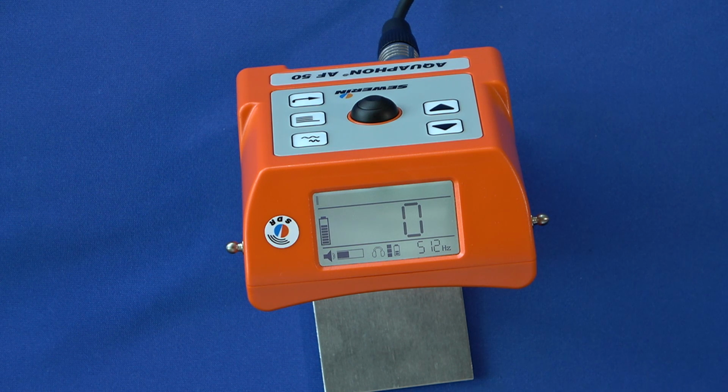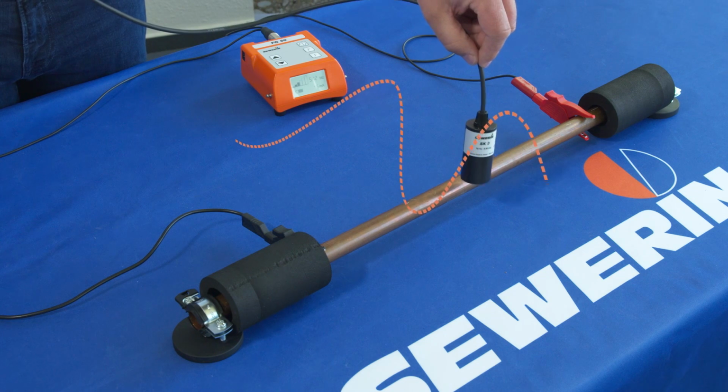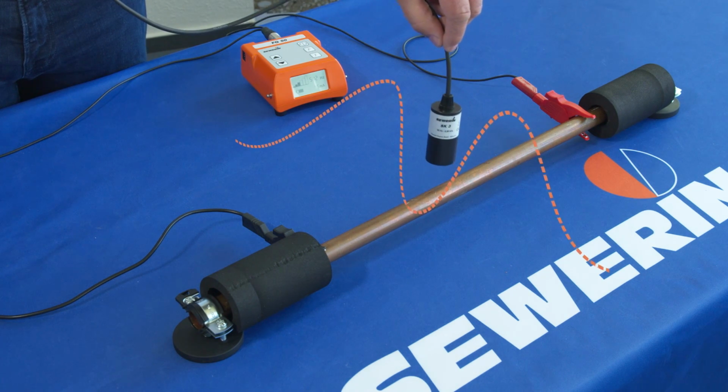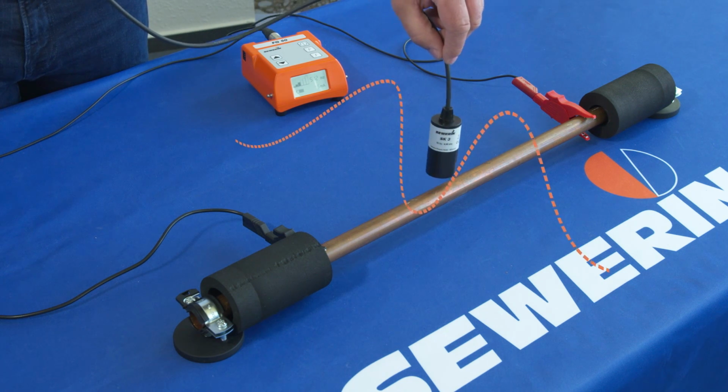The minimum method is suitable for pinpointing or tracking the pipe. The signal falls very strongly and becomes minimal directly above the line. To do this, move the search coil SK3 vertically over the pipe.